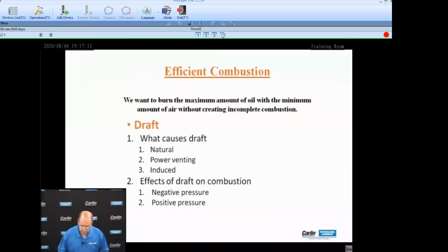Draft. Most people understand how to measure draft, and we know what good draft is, what bad draft is, maybe what too much draft would be. But what are the effects? What causes the draft? How did you make a change? How did you impact the amount of draft that you have on your particular application? Or was it caused by something outside of anything that the equipment has control over? Is there a situation with the chimney? Is there something outside that's causing poor draft? It's not always easy to understand, but it's something that you need to look at and something that you have to know has an effect.